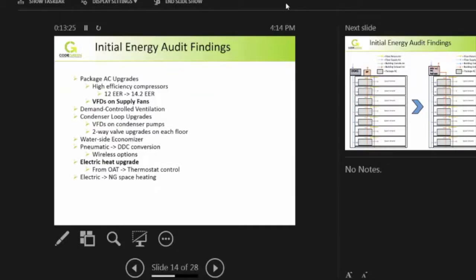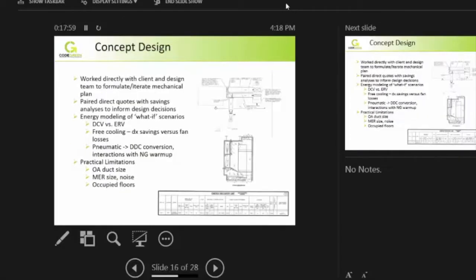Beyond that, going from pneumatic to DDC, upgrading their electric heat from outdoor air control to thermostat control—and a personal pet peeve of mine, electric resistance heat is the worst. It's easy to install, but you end up paying for it for a long time over building operation. Anything we could do to offset electric resistance heat with natural gas space heating would be a net benefit for the building, so we wanted to evaluate that.